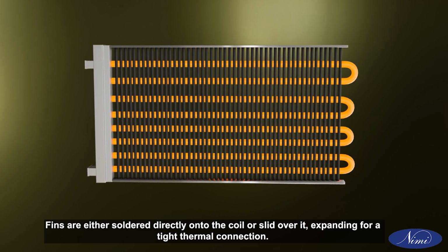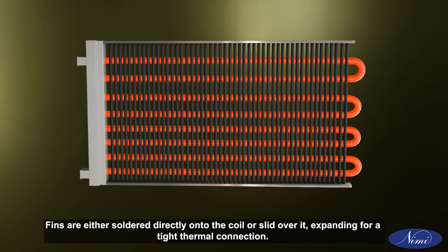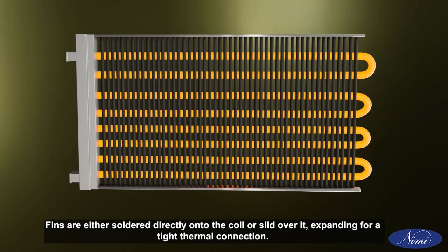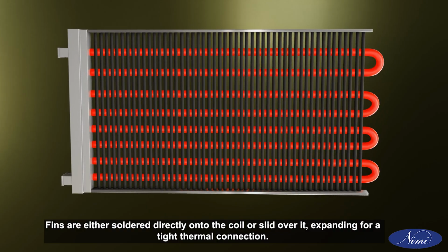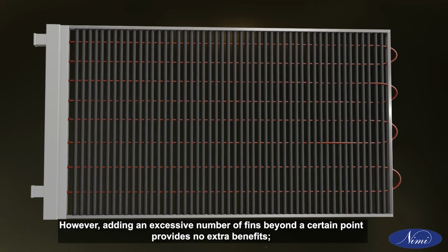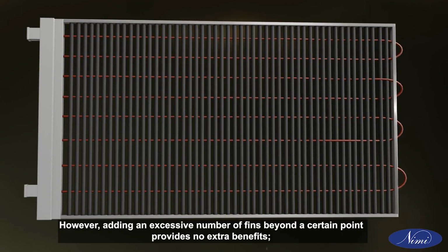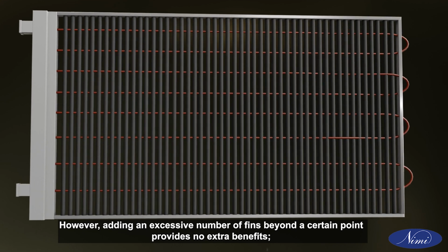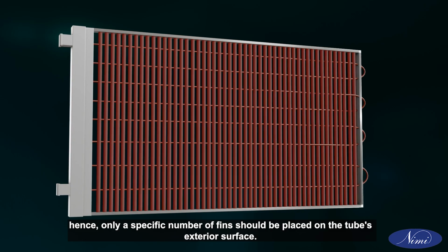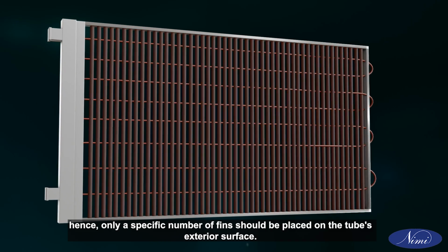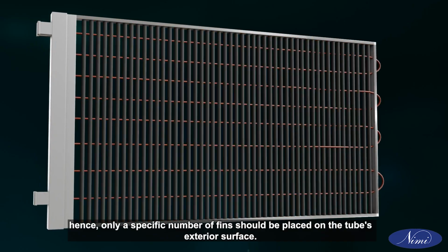Fins are either soldered directly onto the coil or slid over it, expanding for a tight thermal connection. However, adding an excessive number of fins beyond a certain point provides no extra benefits, hence, only a specific number of fins should be placed on the tube's exterior surface.